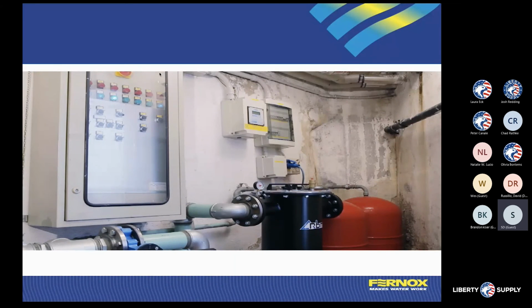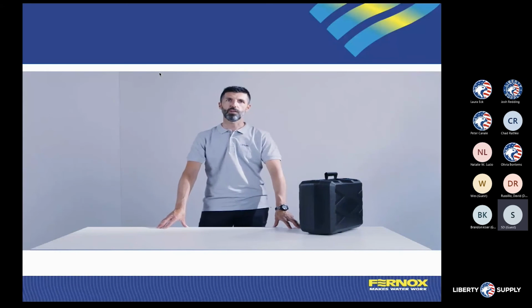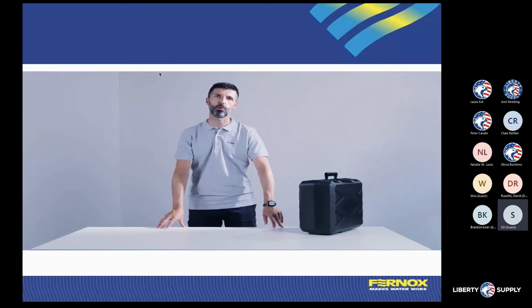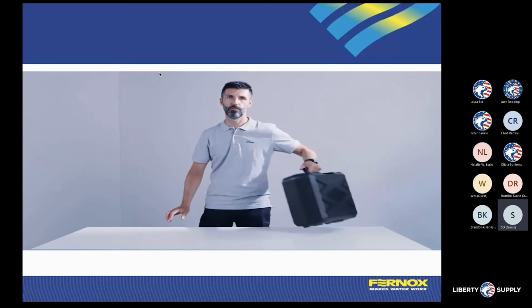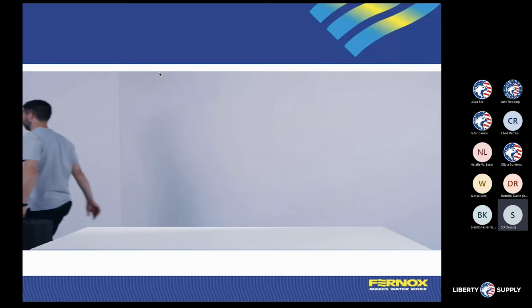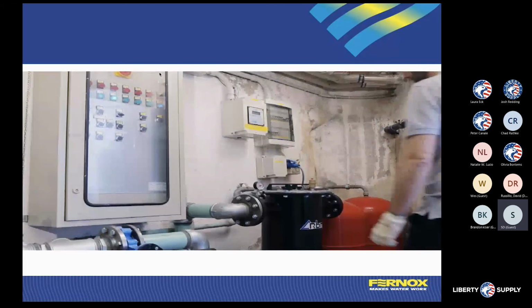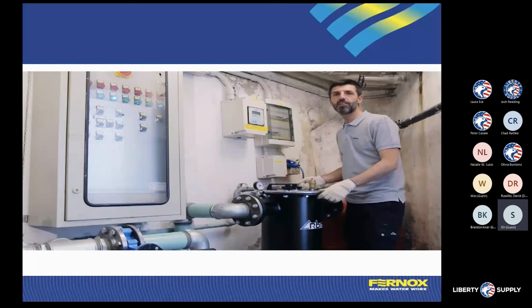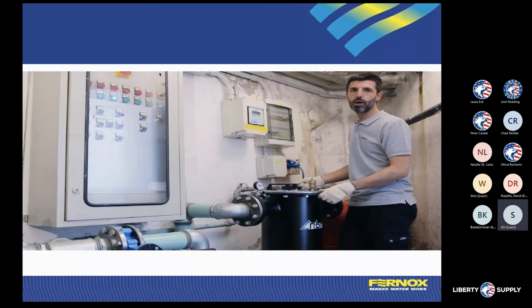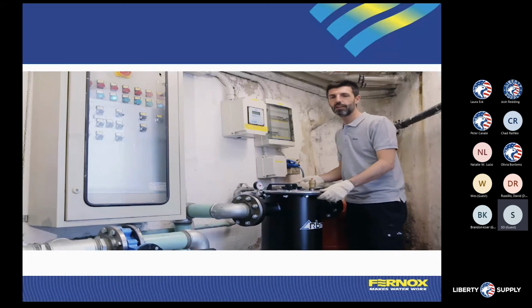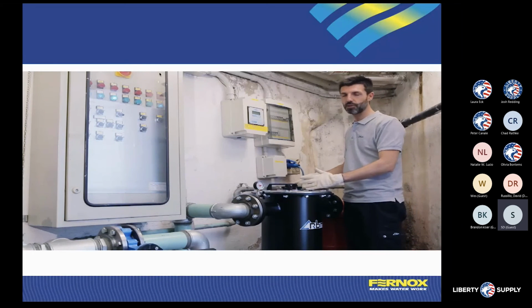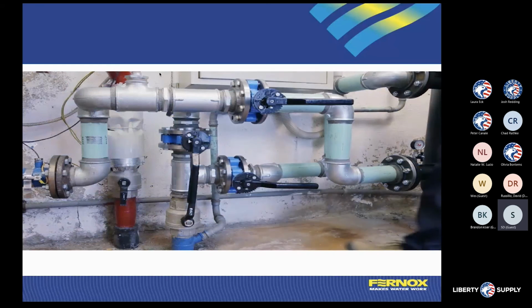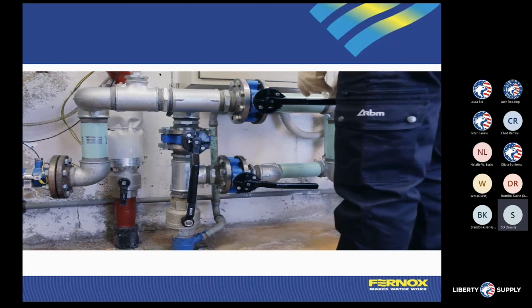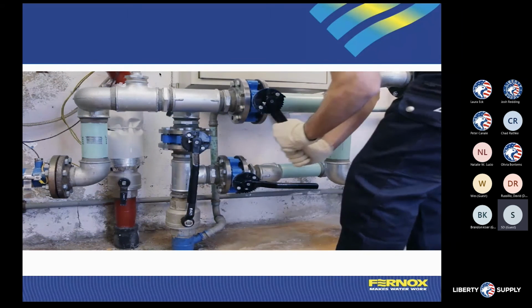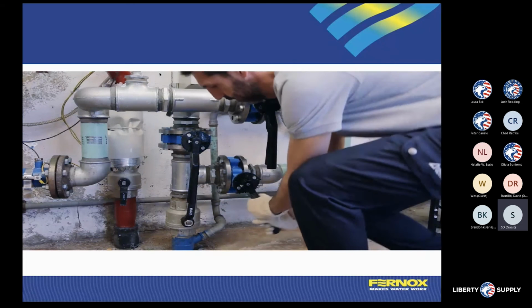When we're talking about magnetic filters, we're talking about pulling that iron oxide out. We're using rare earth magnets inside of a tube or some kind of shield, so the rare earth magnet is not exposed directly to the water. It's separated by some kind of sleeve or covering on that magnetic filter. Because they're rare earth magnets, they're going to have heavy magnetic strength in how we pull that out of the water, or how we hold that solution out of the water.